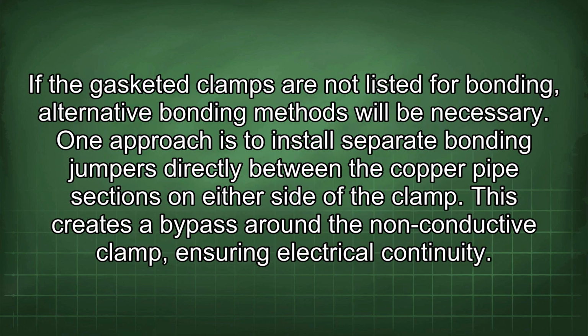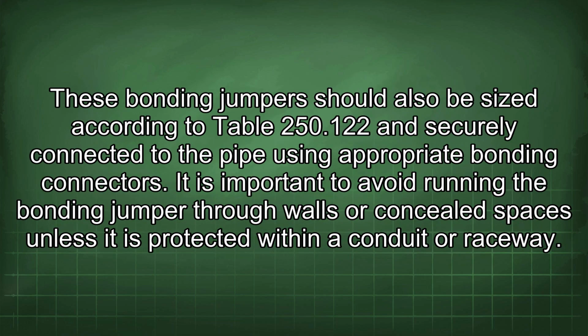If the gasketed clamps are not listed for bonding, alternative bonding methods will be necessary. One approach is to install separate bonding jumpers directly between the copper pipe sections on either side of the clamp. This creates a bypass around the non-conductive clamp, ensuring electrical continuity. These bonding jumpers should also be sized according to Table 250.122 and securely connected to the pipe using appropriate bonding connectors.